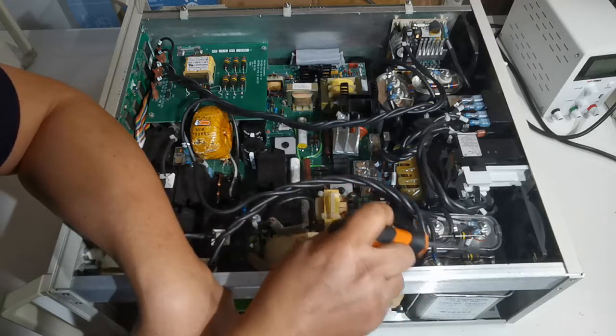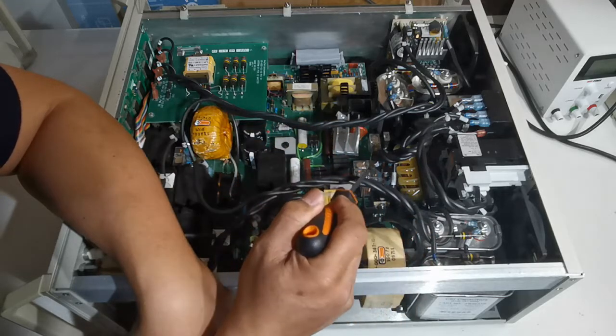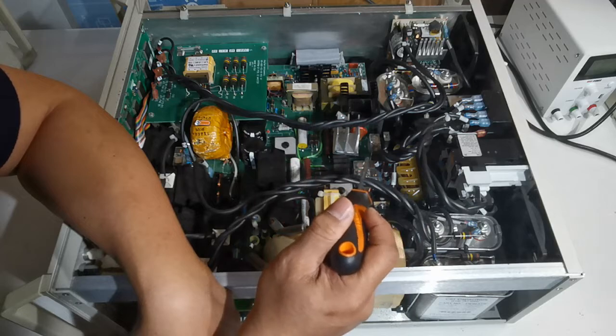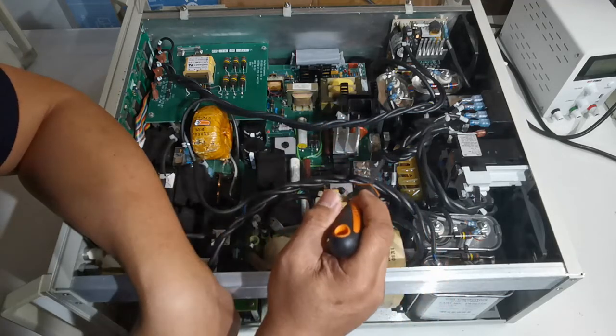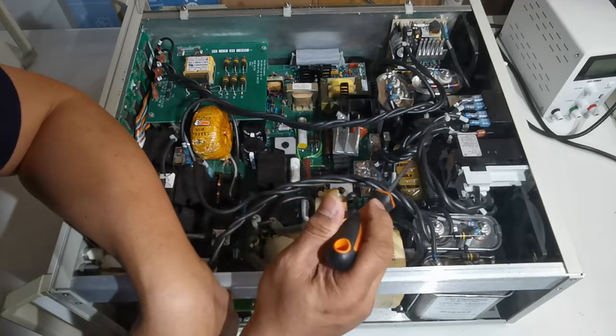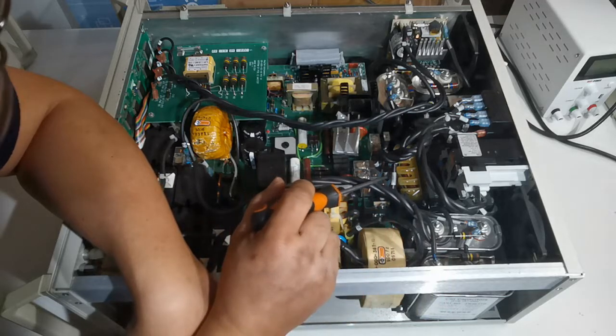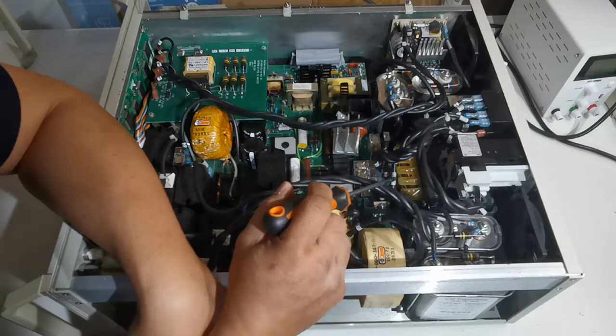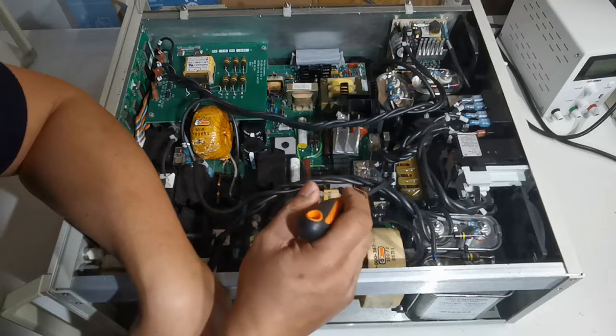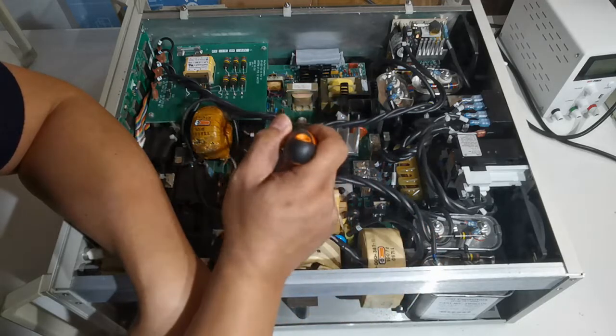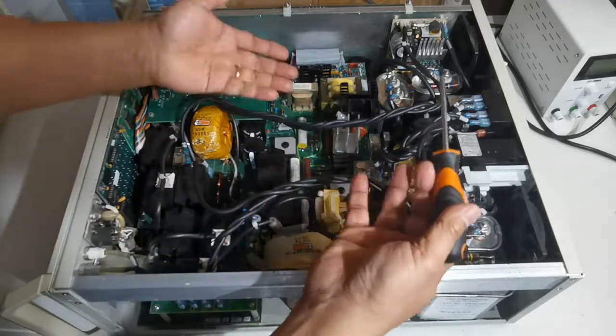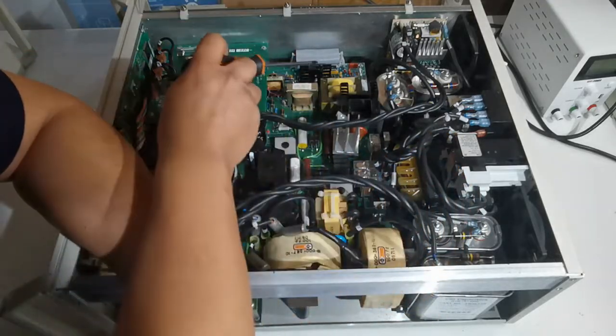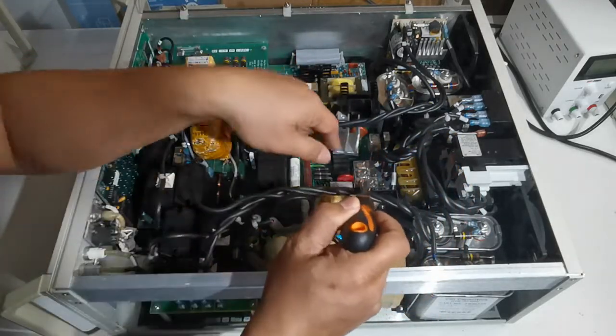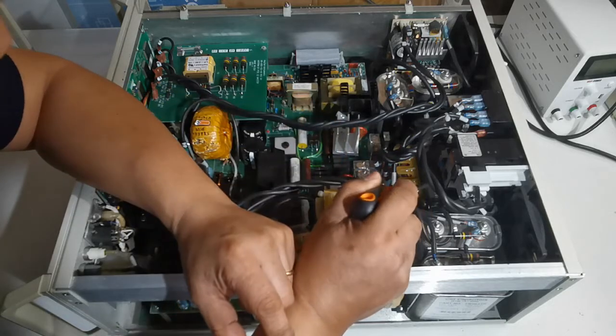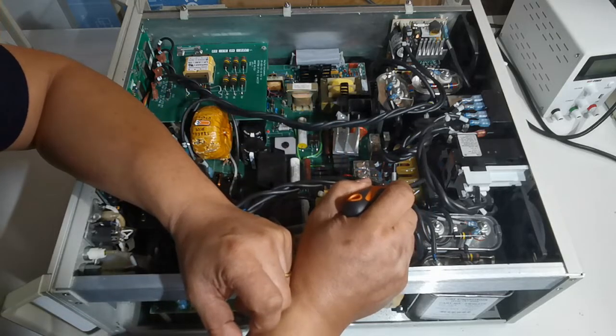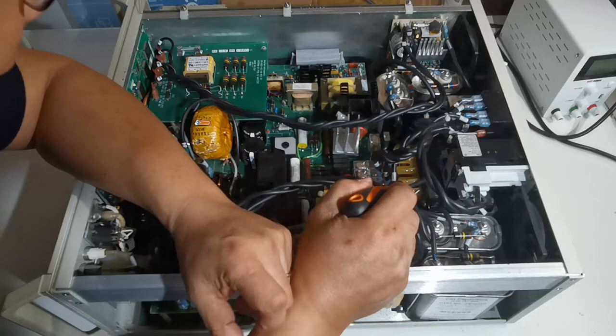So the shaping capacitors and also the other resistors. And we will see where the 2 ohms for line-to-line discharge or surge is, and also the 12 ohms for line-to-earth surge applications. So that is behind this upper board. This big inductor here is the auto transformer.